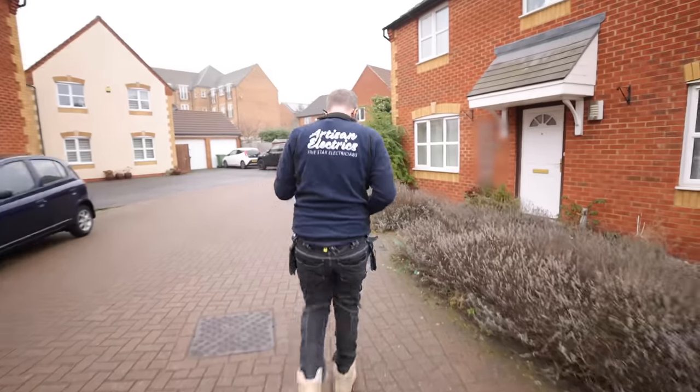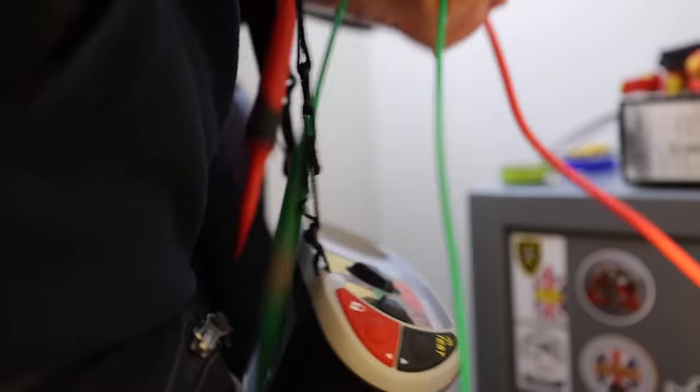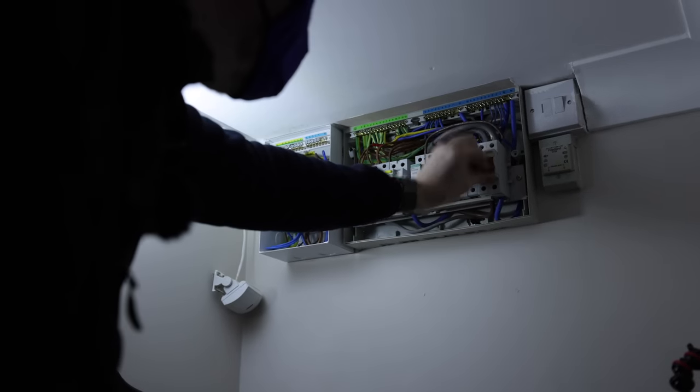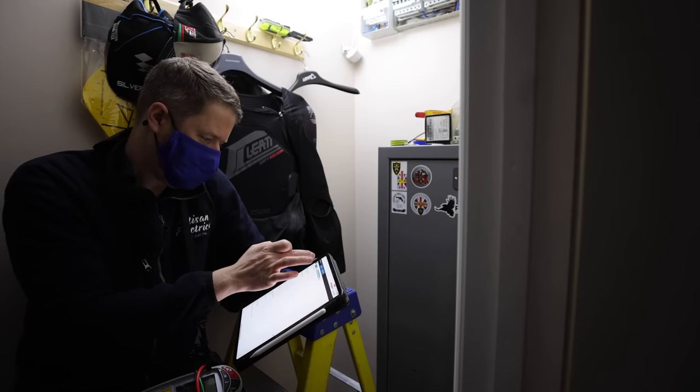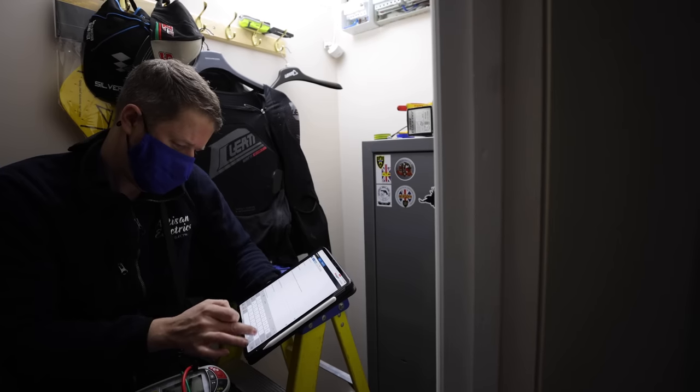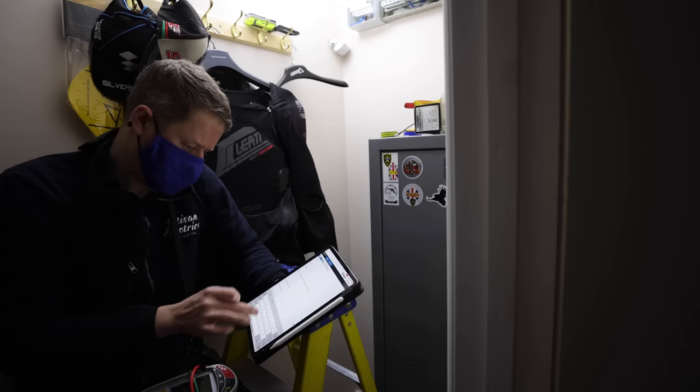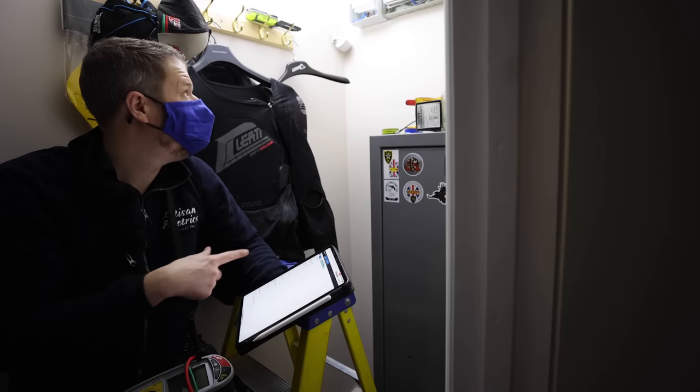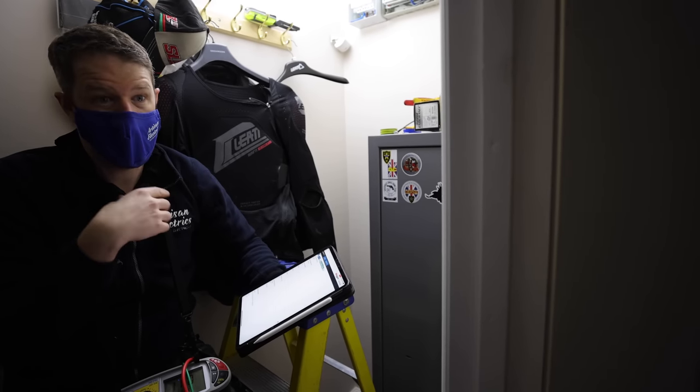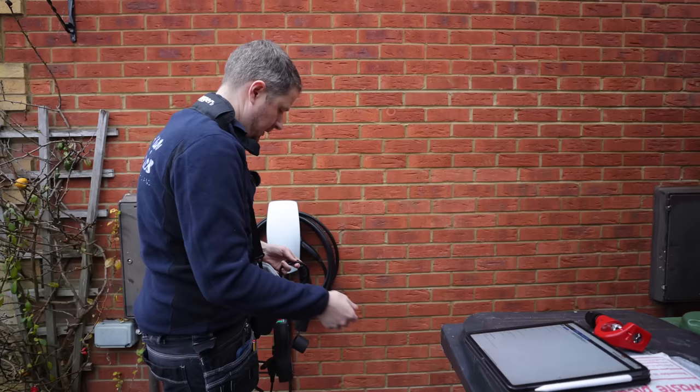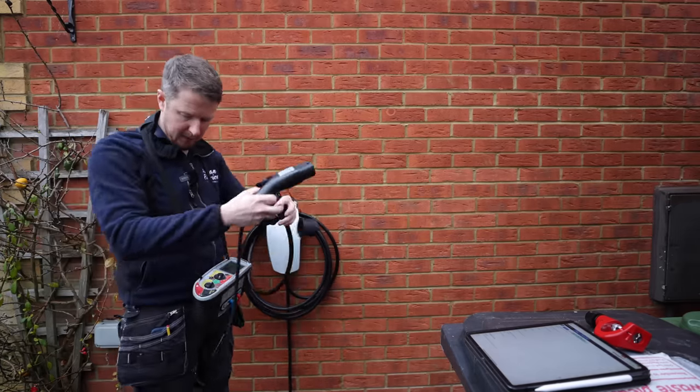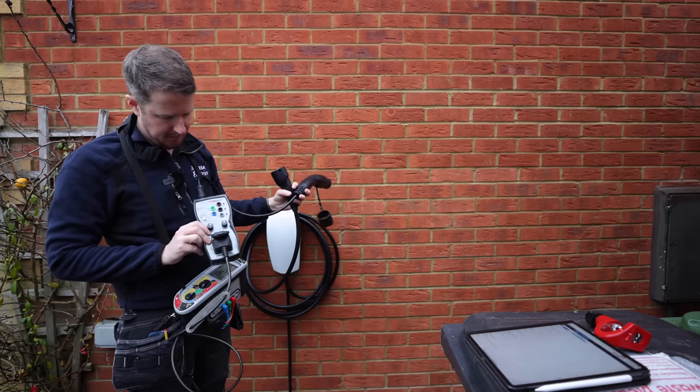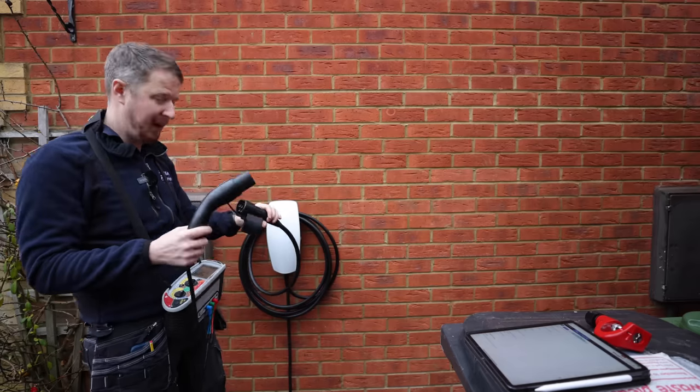So we're going to now input our Ze and PFC readings, so we've got 0.11, pop that in. PFC was 2.13, so that's all good. So now we can liven it up, and then we'll do our Zs and our RCD tests and our functional tests.